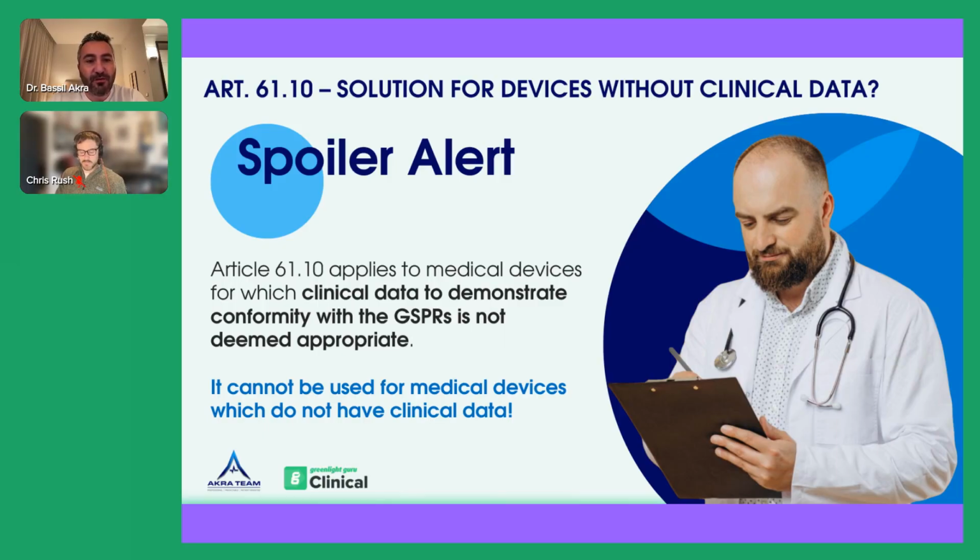So you need to understand your device, describe that device, its functionality, its characteristics, its performance criteria, and then define what would be necessary to show that that device is performing as intended, is safe, and has the relevant clinical benefit which is required by state of the art to be delivered with such a device. And then based on that, you define your clinical strategy. The regulation gives you an opportunity to have devices approved based on no clinical data. You still have to write a clinical evaluation, but that clinical evaluation doesn't require inclusion of clinical data in it.